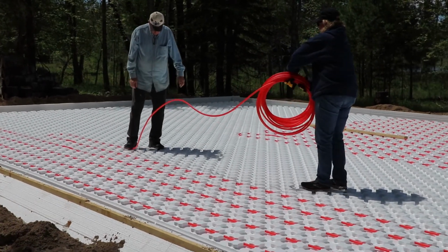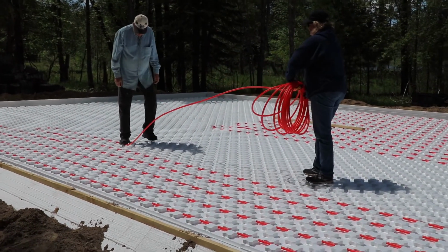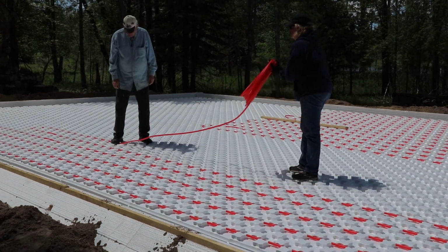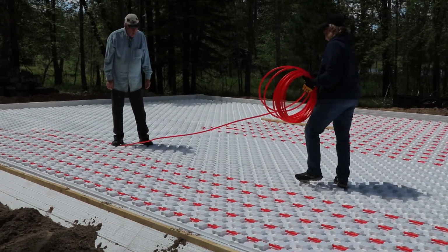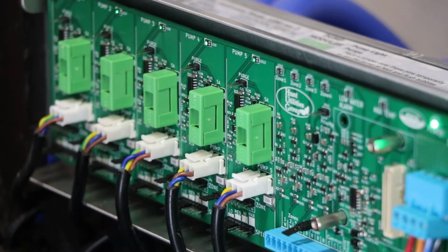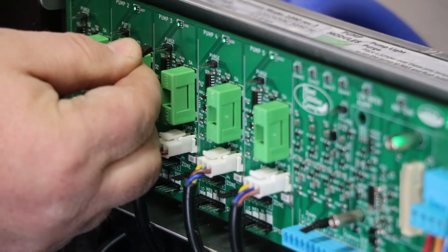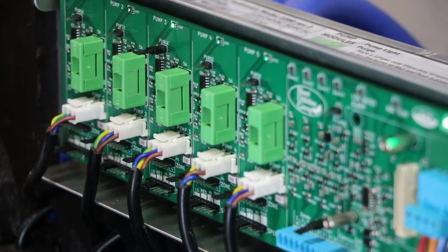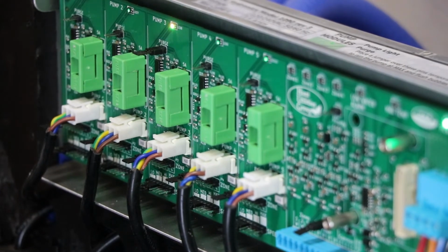Each 300-foot PEX loop holds about 3 gallons of fluid. The tank holds about 8 gallons in addition to the fluid in the loops. Not all of your fluid will fit in the tank at first. You will be adding more fluid as you purge the loops.